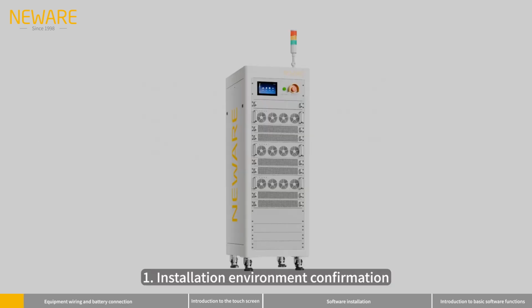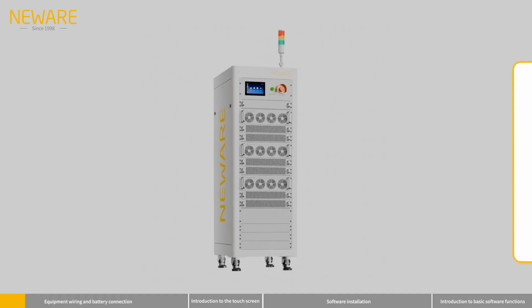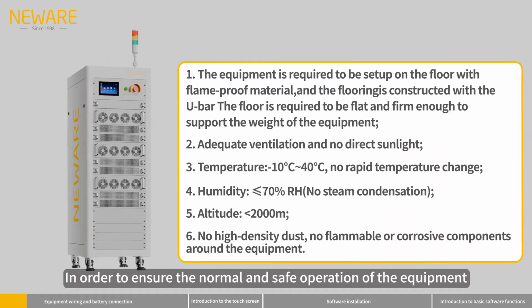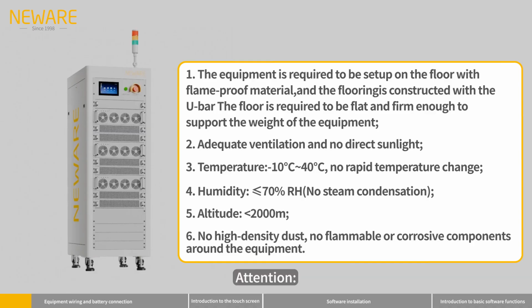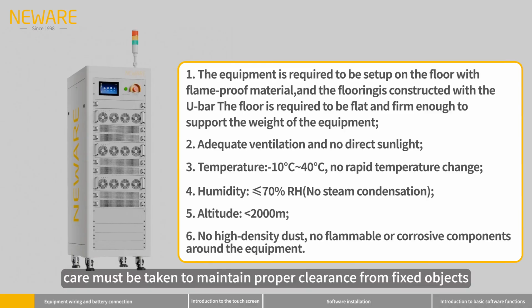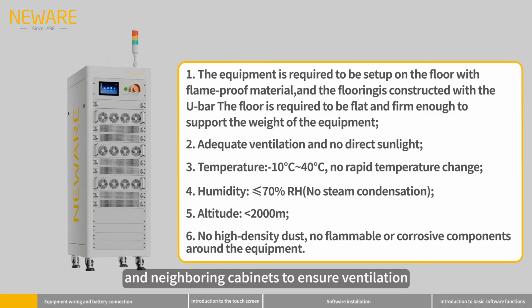1. Installation environment confirmation. In order to ensure the normal and safe operation of the equipment, please make sure that your site meets the following requirements. Attention! 1. When installing the equipment, care must be taken to maintain proper clearance from fixed objects, e.g. walls and neighboring cabinets, to ensure ventilation and safe escape in the event of danger, and at least one person should be left with space greater than or equal to 600 mm to pass around the equipment.